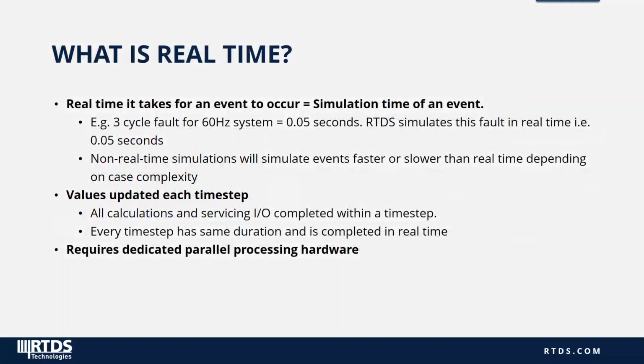So we know the type of simulation we're dealing with. What does it mean to operate in real time? Well, the real-time aspect is really what separates the RTDS simulator from offline or non-real-time EMT programs, such as PSCAD. And when we say real-time, we mean the computer needs to solve all of the equations for the network in real-world time equal to or less than the simulation time step. So this means the real time for a power system event to occur is equal to the simulation time.